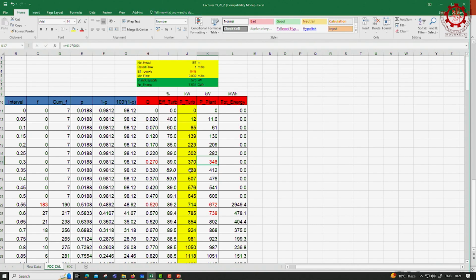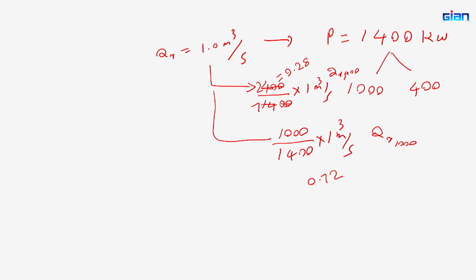But now beyond that, if there is more water still, now this we use when the flows are very low, right. And on the other days we can start to use the next machine, and then you have to go on calculating for that one separately. But now our selection does not seem to be very sensible here, because there are no days on which the flow is so low. All of them are very little. Therefore, maybe we can think of having two similar units, rather than having 1400, we can have 700 into 2 probably. We can try that option also. 700 kilowatt into 2, right. So, that is an option.